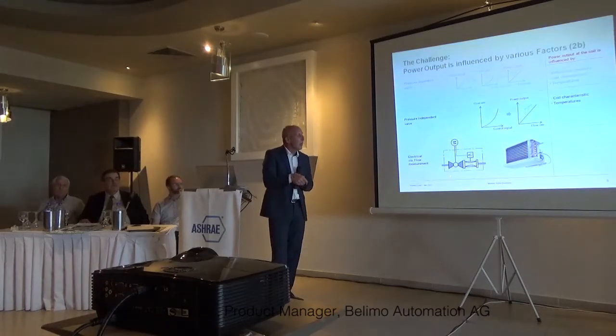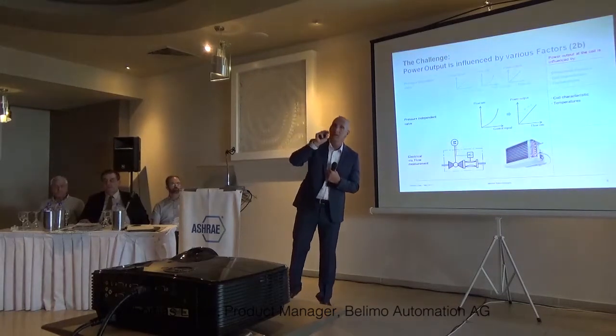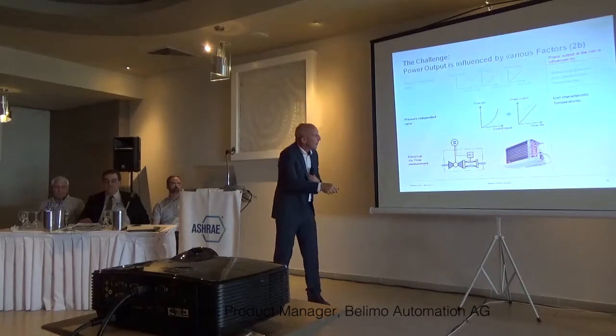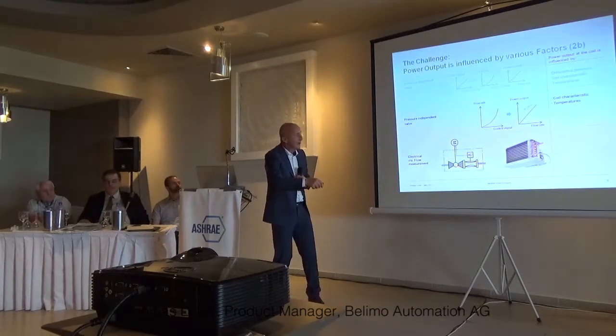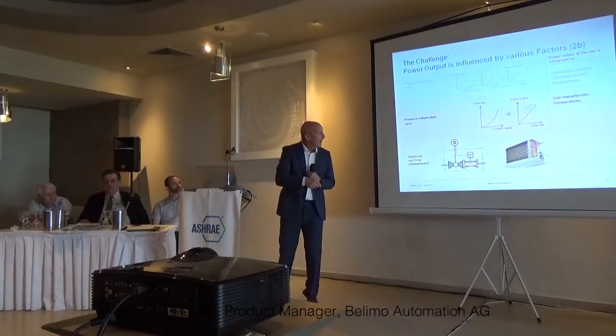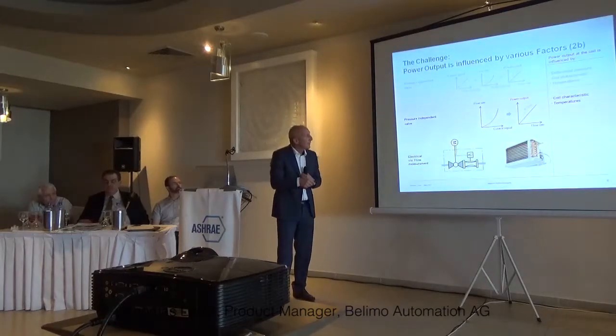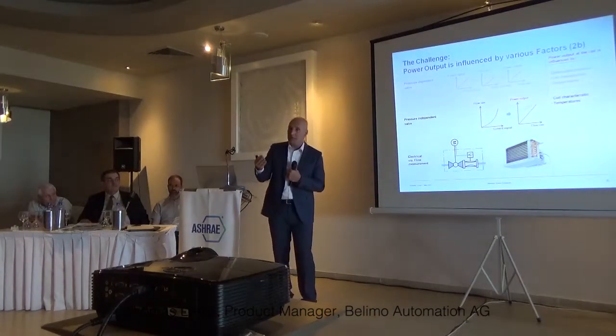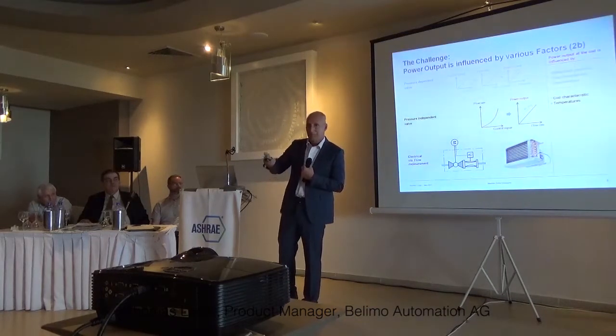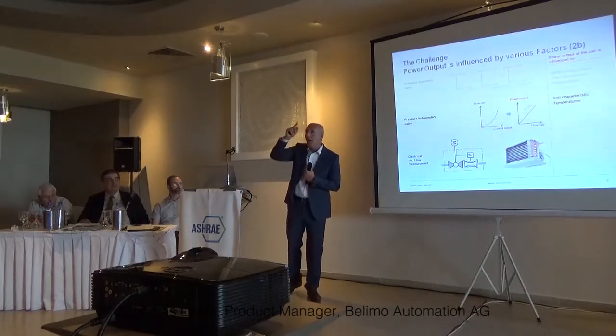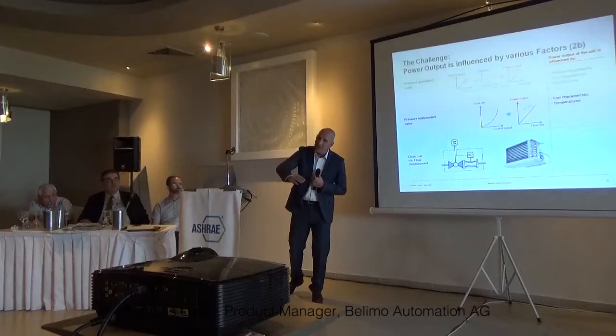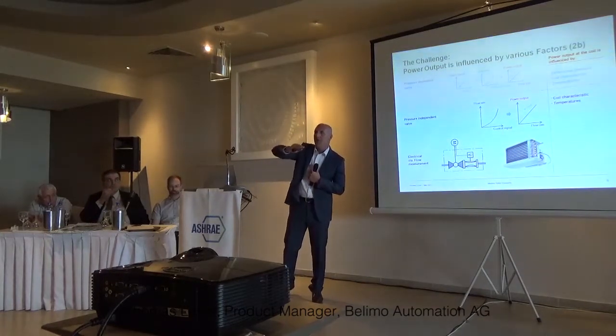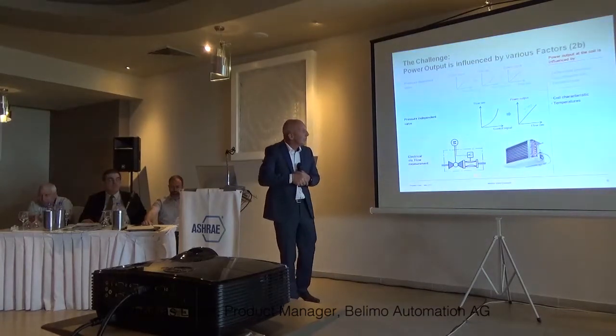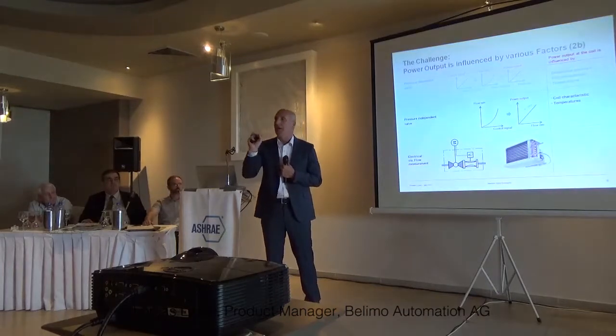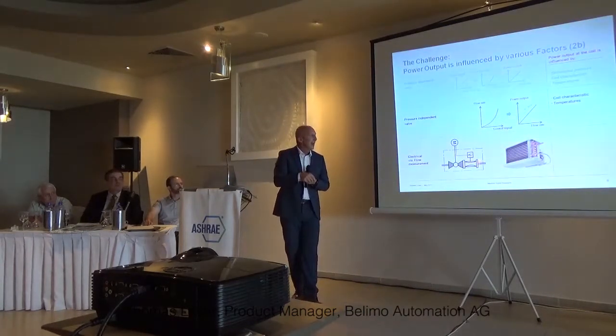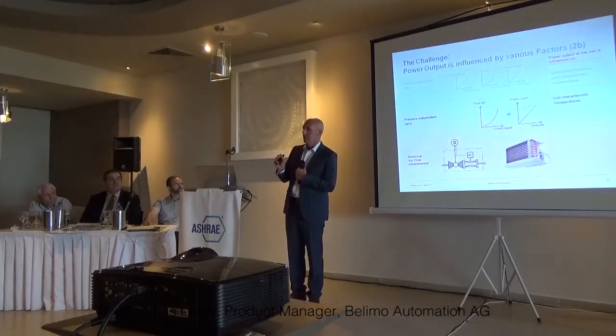So the valve will know exactly what the output should be. The water is flowing from this side. I measure my real flow, what is going on. I know this is, let's say, 93. My valve should actually bring just 75, as an example. So the valve will immediately know, the flow is too high. I have to reduce it. With the actuator, I close my control valve, and so I can maintain exactly the proper flow. So the main difference here is the fact that I measure and I know what is going through the valve. I definitely measure. It's important to know.